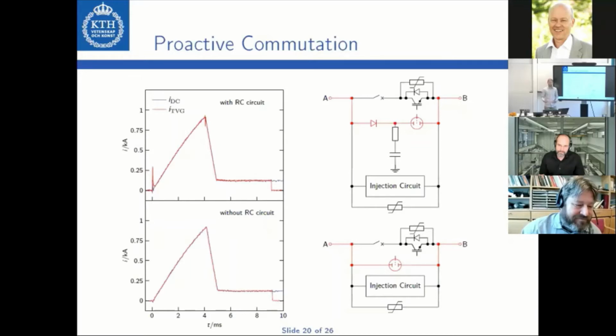The arc voltages of all the modules would add up by the number of connected modules. As part of the experiments, for practical reasons, we used the triggered vacuum gap. If you used a different triggered spark gap, for instance with SF6, the arc voltage could also be increased, which would speed up the commutation process. So there are many design parameters which affect this and which can also make it faster at HVDC.